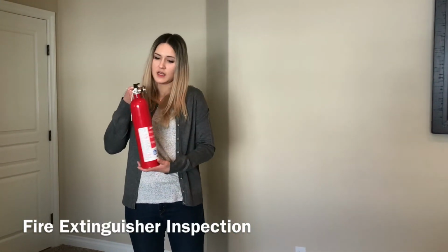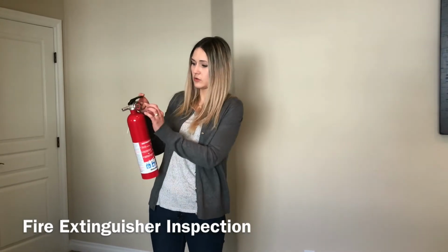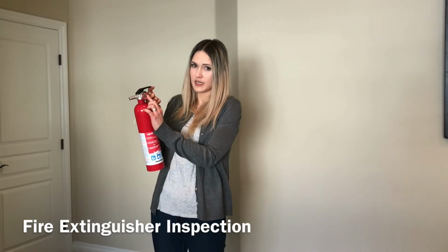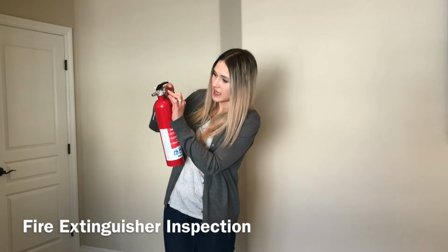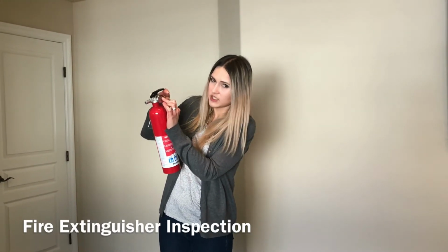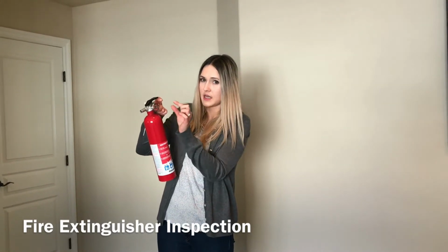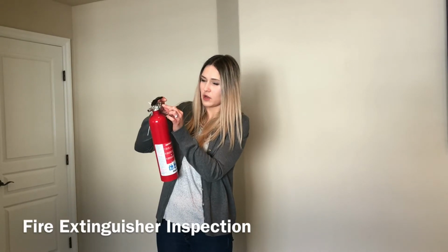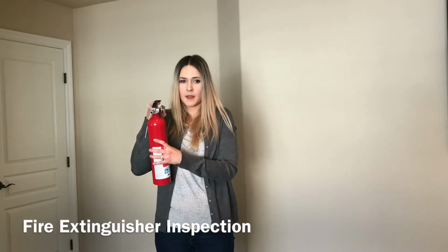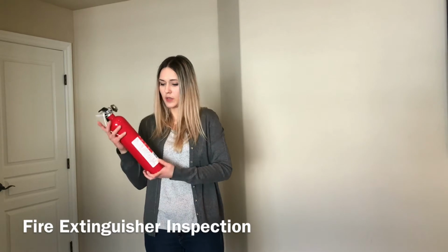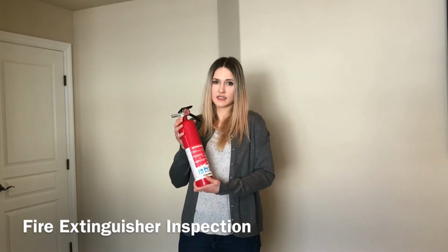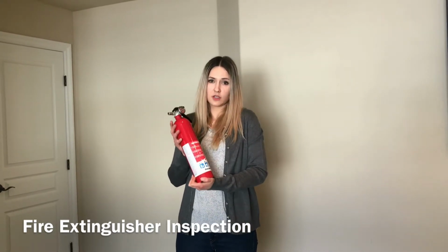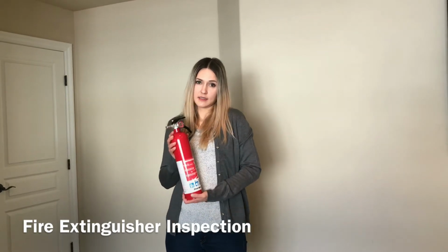Next, we have to ensure that there is no physical damage to the fire extinguisher, that the nozzle is not leaking, and there is no corrosion on it, so it's safe to use in case of fire. Another important thing is the pressure gauge. We need to look at it and make sure that the pressure pin is indicated, that the pressure is right to use. It's in the green spot on the gauge. And the last thing, we need to ensure that the fire extinguisher is full. In order to do that, we just need to weigh it in our hands.